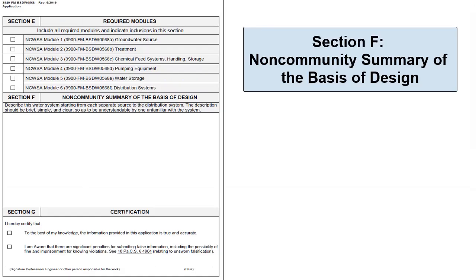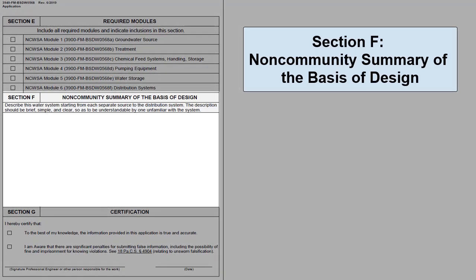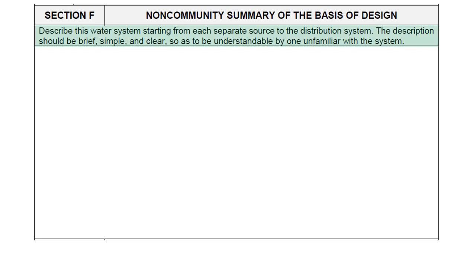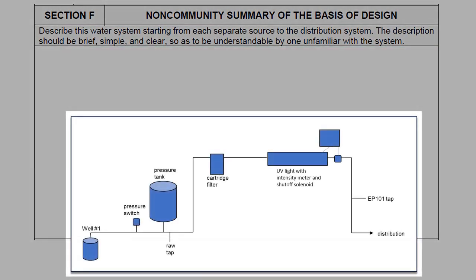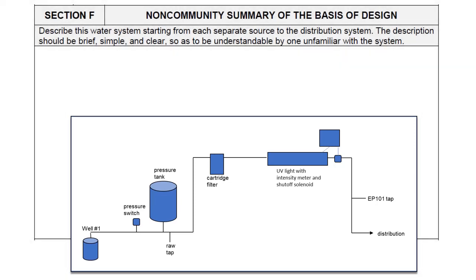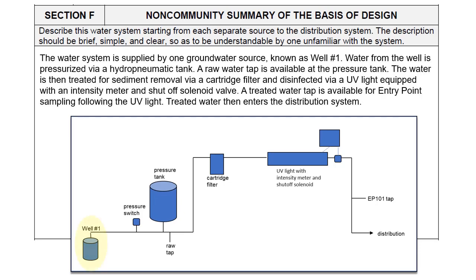Section F, Non-Community Summary of the Basis of Design, shall include a written description of the water system. The written description shall start at each source and continue through to the distribution system. Here is a schematic for a system with a well, cartridge filter, and UV light. The written description of this system might be: the water system is supplied by one groundwater source known as well number one. Water from the well is pressurized via a hydropneumatic tank, and a raw water tap is available at the pressure tank. The water is then treated for sediment removal via a cartridge filter and disinfected via a UV light equipped with an intensity meter and shutoff solenoid valve. A treated water tap is available for entry point sampling following the UV light, and treated water then enters the distribution system.